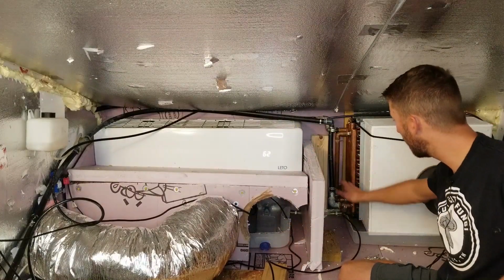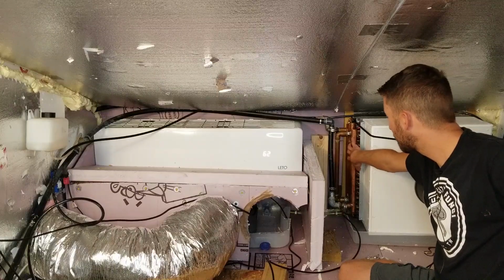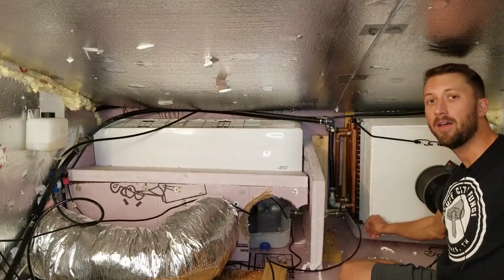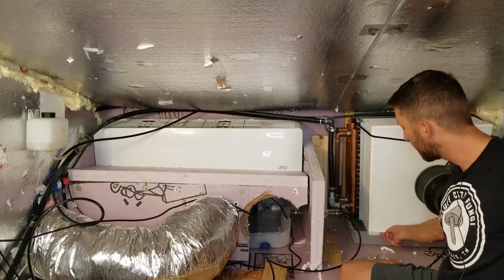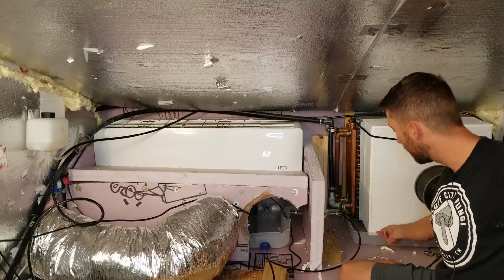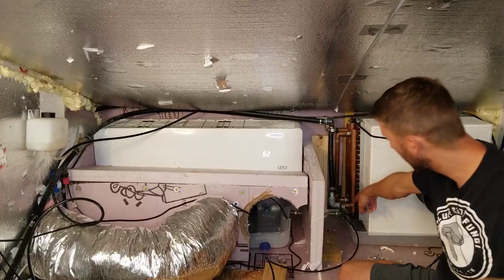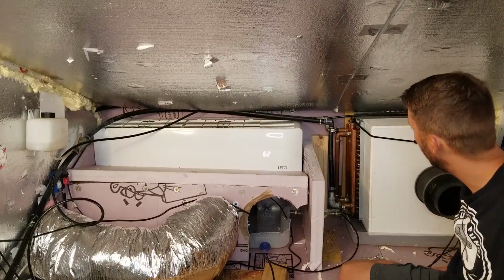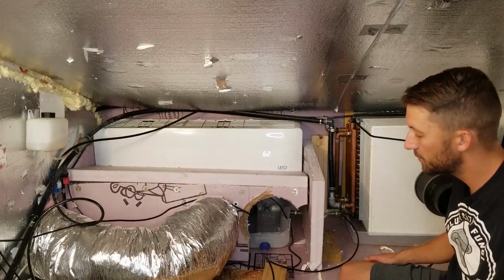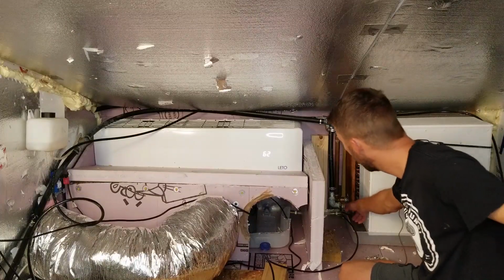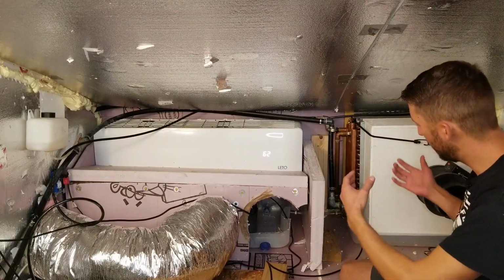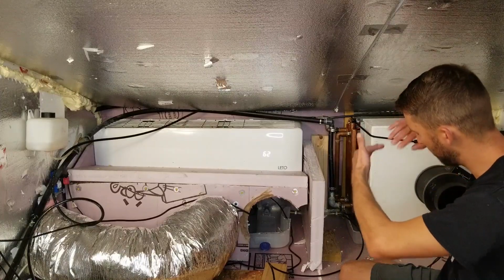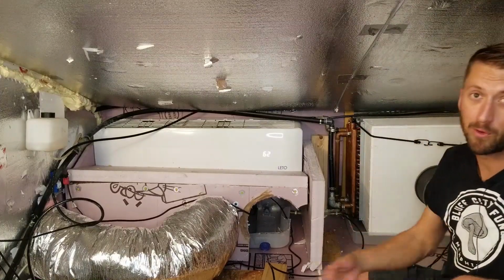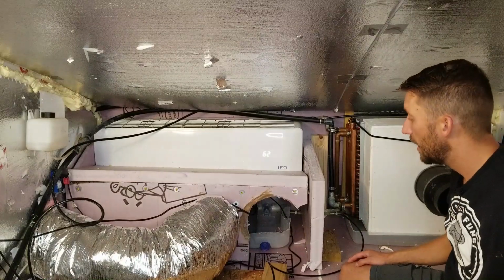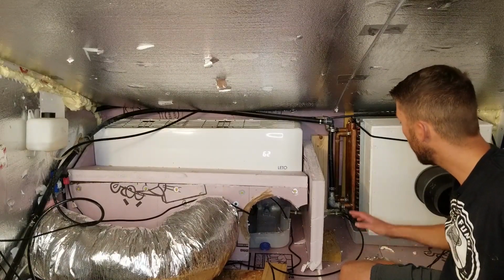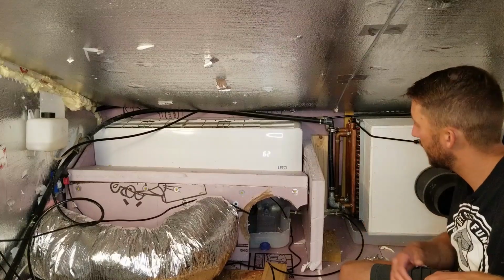On the HRV system, you also have to put a pan under that. So I have another drip pan that I made out of a tote, and I put a bulkhead fitting over here that goes outside. It's really important you get the moisture out of here. I actually had an issue where this wasn't high enough, and the water was dripping around it, going underneath, and I had to rip up the whole floor and redo it because there was water damage underneath. That was my summer. So make sure you have drip pans on everything that's going to be leaking.